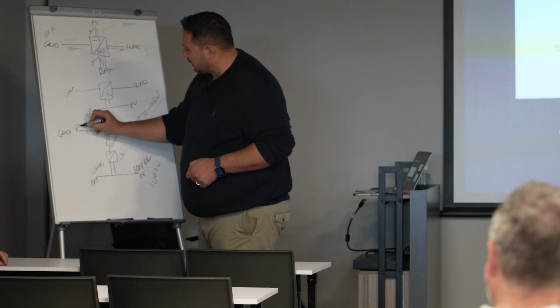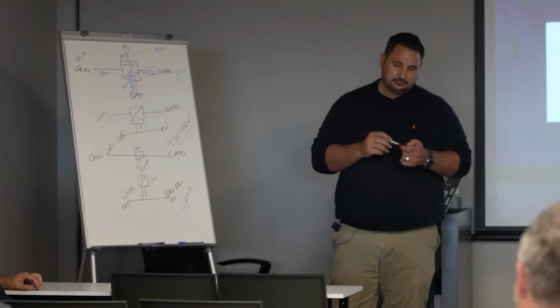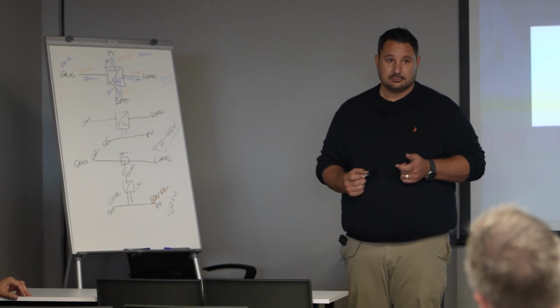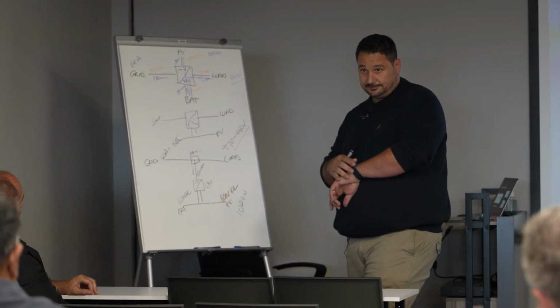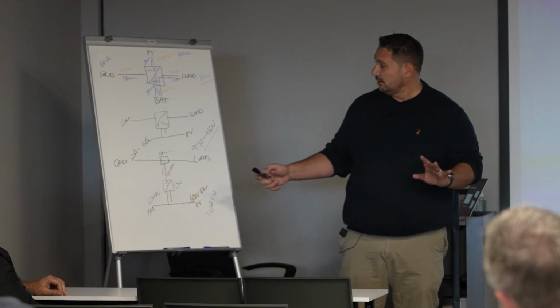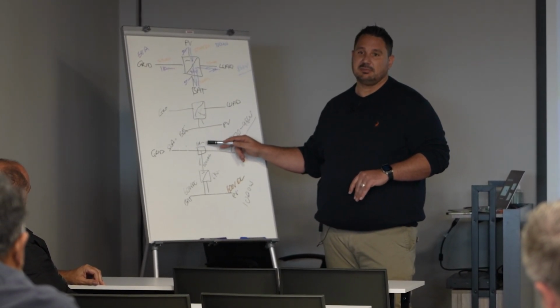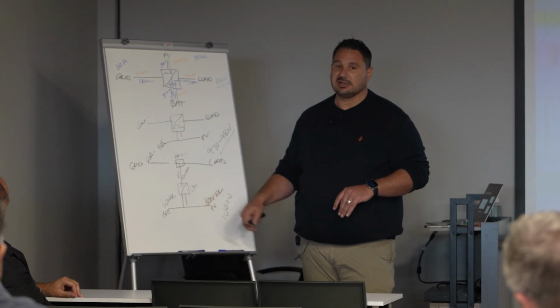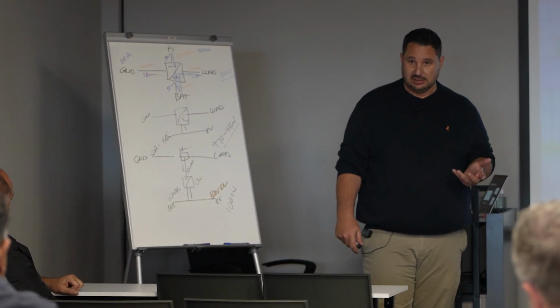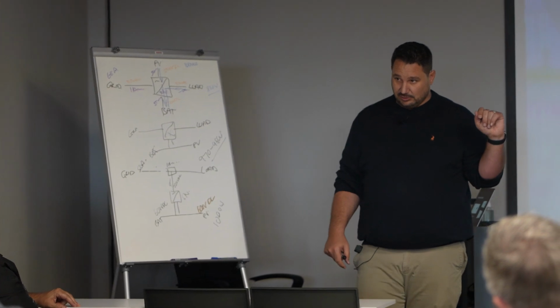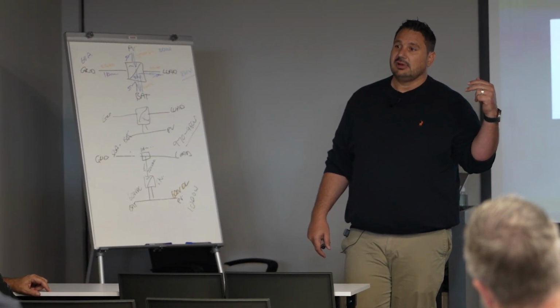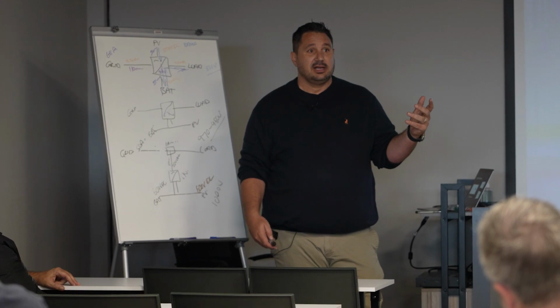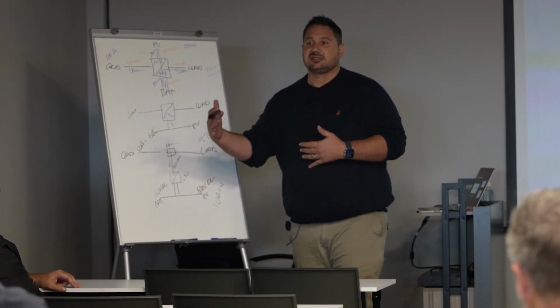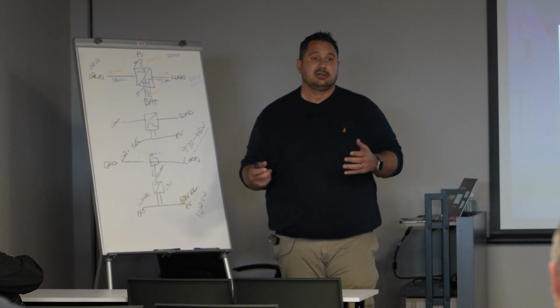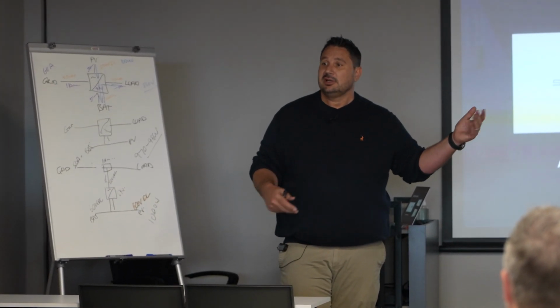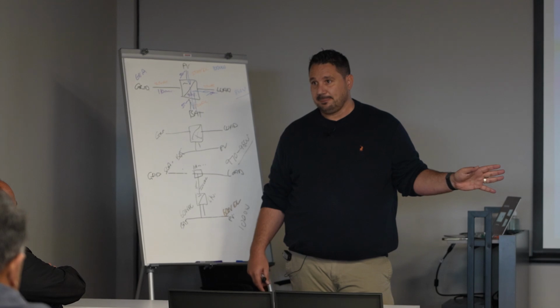If you've got a 6 kilowatt inverter here, and you have got an 80 amp connection over there, you can draw 100 amps when the grid is available. Again, understand that that is a 110 mil pipe, that's a 50 mil pipe. If we shut off that 110, we've got the limited flow of the 50. That is why the smart port is inside the gateway, so that you can connect your heavy loads to the smart port or a generator, and you can then say, if the grid fails, start the generator just to handle peaks, or just put my peak loads on the smart port. When the grid fails, just drop them out and don't use them.